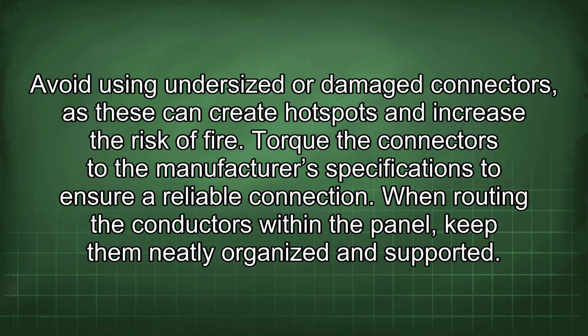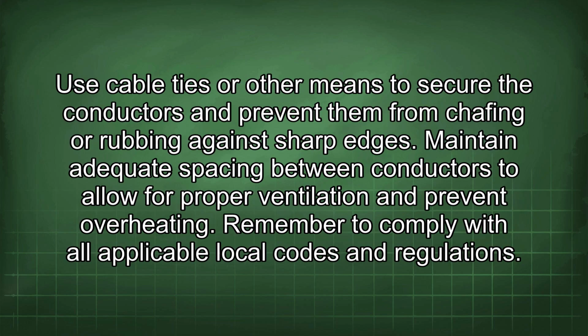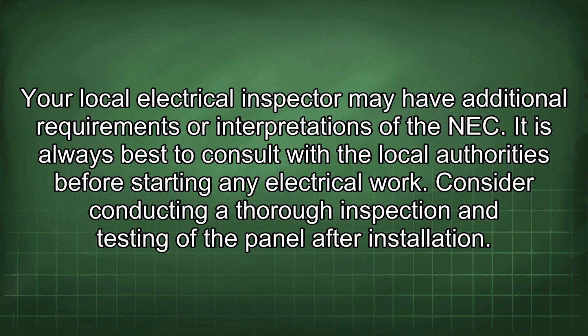When routing the conductors within the panel, keep them neatly organized and supported. Use cable ties or other means to secure the conductors and prevent them from chafing or rubbing against sharp edges. Maintain adequate spacing between conductors to allow for proper ventilation and prevent overheating. Remember to comply with all applicable local codes and regulations. Your local electrical inspector may have additional requirements or interpretations of the NEC. It is always best to consult with the local authorities before starting any electrical work.